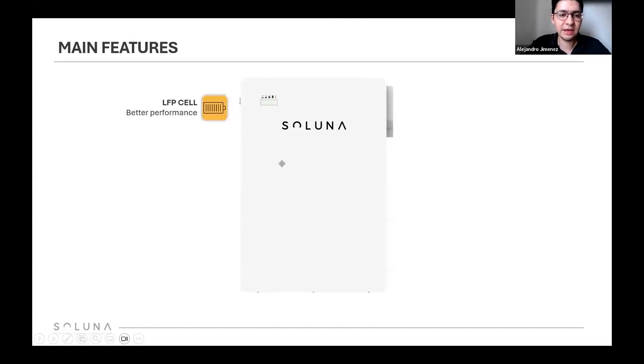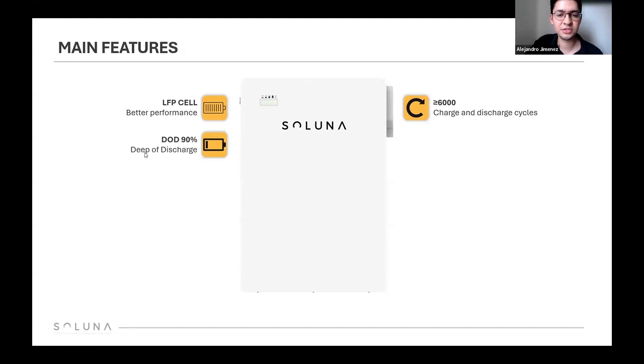The cell is the same technology, the same chemistry, LFP cell. The difference between the HV and LV battery is the cell structure. In the HV battery we use cylindrical cells, and in the low voltage battery we use prismatic cells. The difference is the form, but the chemistry or technology is the same. We have the same cycle life, most of the 6,000 cycles of charge and discharge. The DOD, depth of discharge, is the same. We can discharge the battery up to 90%.